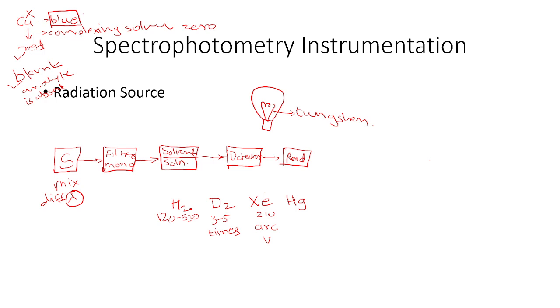The slits control the amount of incoming and outgoing light, and the devices take the advantage of Beer-Lambert's law. Interference of light is avoided and sensitivity of measurement is increased. Okay, so in this way you can control the radiant power.